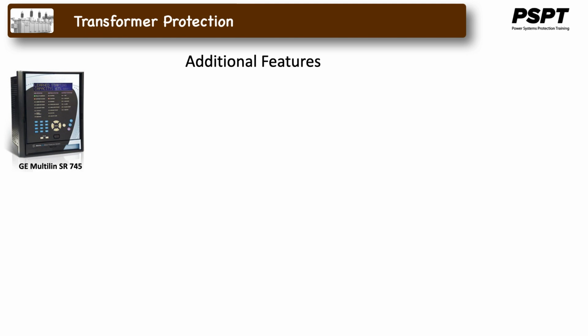Additional features for the 745 include negative sequence overcurrent. For delta-Y impedance grounded transformers, overcurrent protection is particularly difficult to set. A negative sequence based overcurrent element provides the required sensitivity.